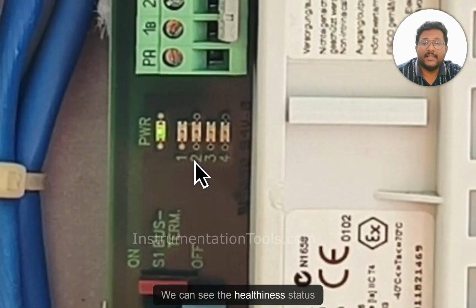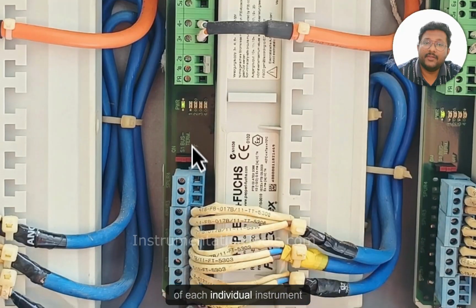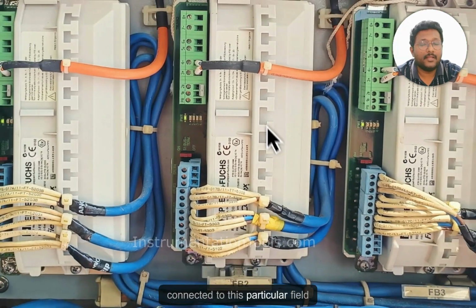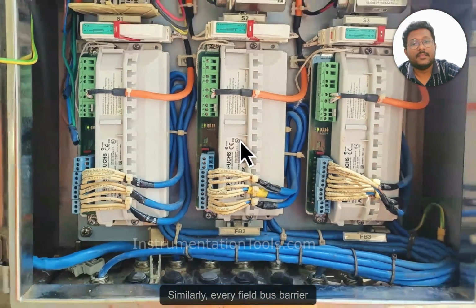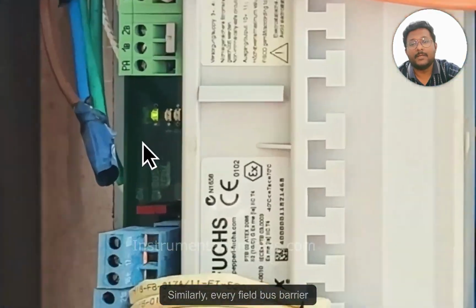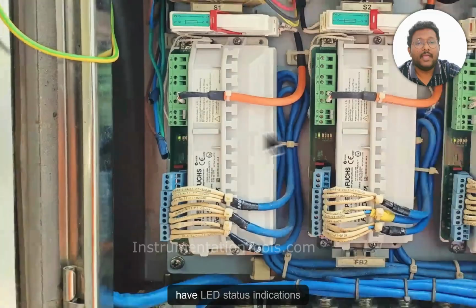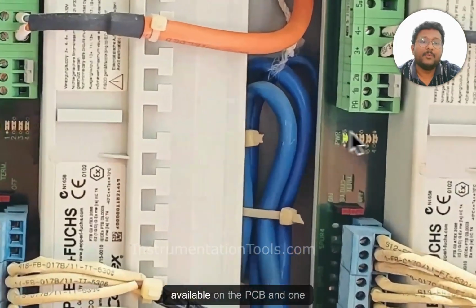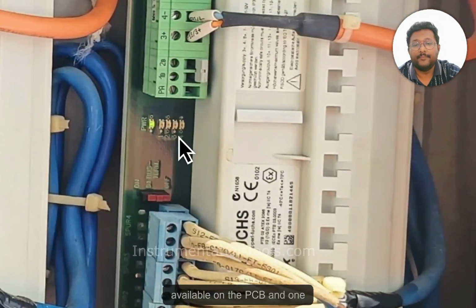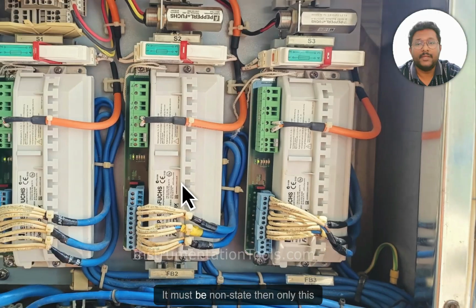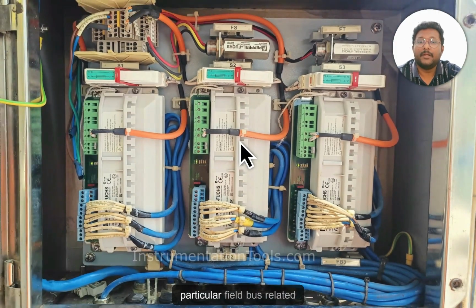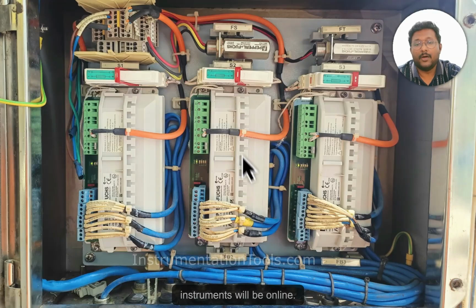We can see the healthiness status of each individual instrument connected to this particular field bus barrier. Similarly, every field bus barrier has LED status indications available on the PCB, and one terminate on-off switch is also available. It must be in the on state, then only the instruments related to this field bus barrier will be online. Otherwise, they will not work.